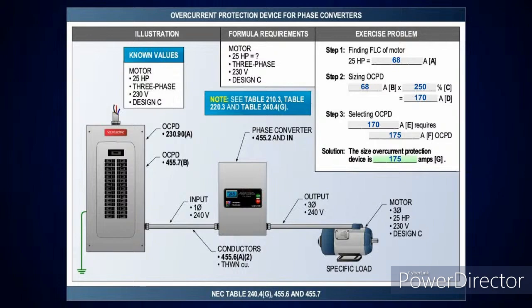230 volts, come down, pick up 25 horsepower. It's going to tell you it has an amperage rating of 68 amps. And then 455.6(A)(2) is going to tell you take it at 250%, which gives you 170 amps. And the next size above that to protect that conductor is 175 amp overcurrent protection device.